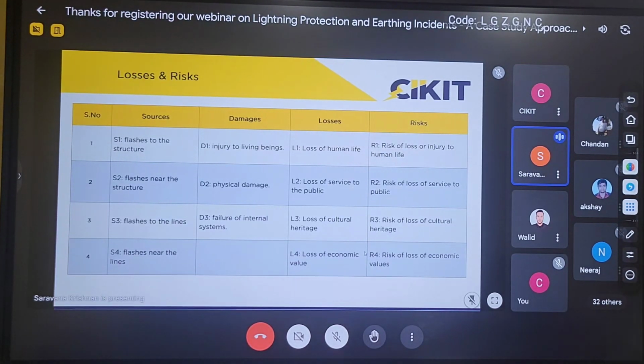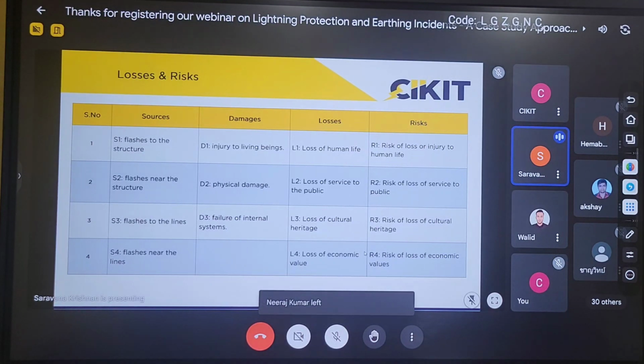And regarding the corresponding sources of lightning, there are mainly 4 different sources that cause damage to the buildings. We have explained about the sources, damages and losses in detail in the separate video. Since we have to discuss lightning protection system designing and earthing also in the same webinar, I'm just skipping this topic. There are 4 different sources that relate to the damage: flashes to the structure, second, flashes near the structure, third, flashes to the lines, and fourth, flashes near the line. These are the 4 sources that cause damages, and the 3 damages are injury to human beings, physical damage to the structures, and failure of electronic equipments. So in risk assessment, we will be calculating the risk due to lightning on the particular site conditions, and what are the preventive measures that we can take for reducing the losses due to lightning.